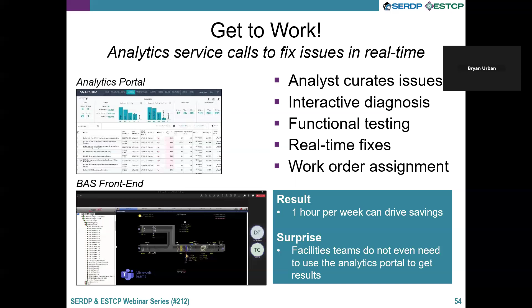With a very limited amount of time, one hour a week, we were able to drive a lot of the savings. In some cases they had to issue work orders to send a technician out to check a sensor in the field or make an adjustment, and we'd come back the week after or in a couple weeks to see if the problem had been resolved, or take a next step. Having a routine, getting into a rhythm, and getting to know the facilities teams was really key to making big strides on these issues and getting things actually fixed.